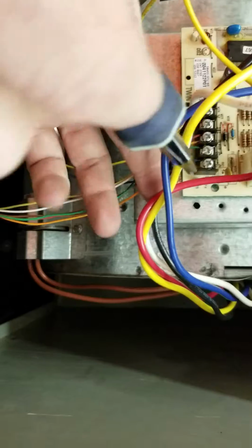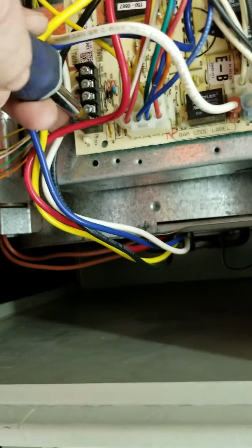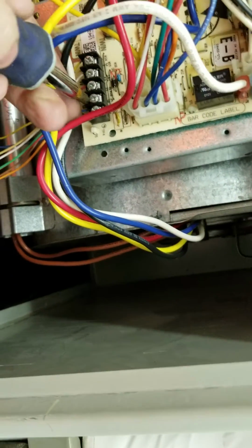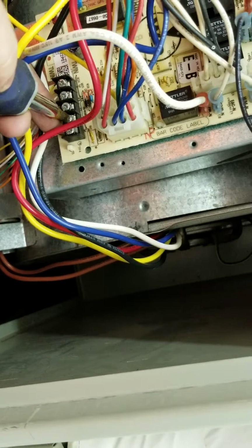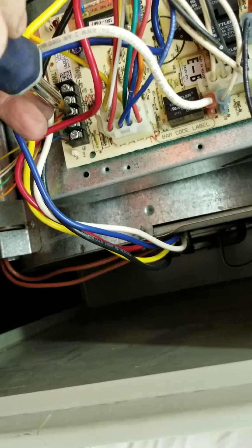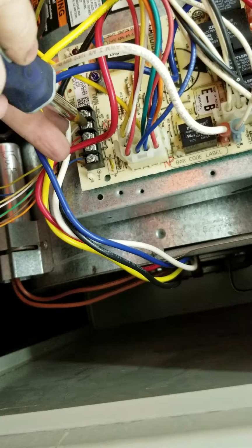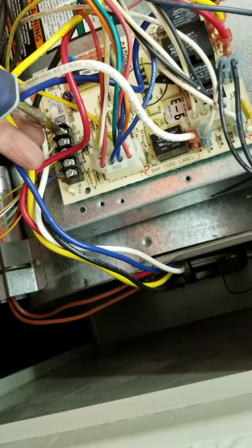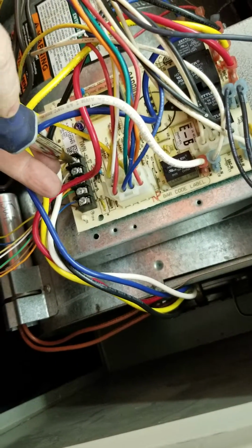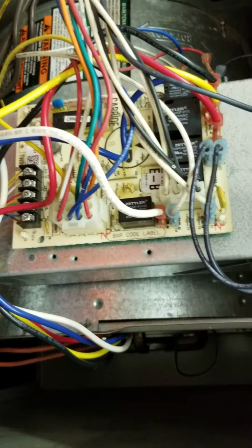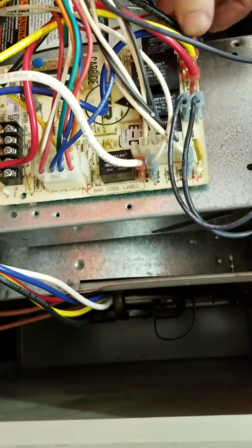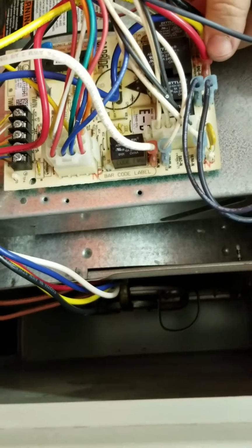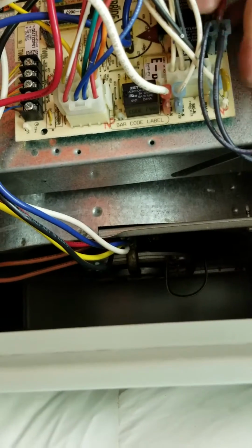Okay, now double check your connections, your control connections here at the furnace. You don't have to be real hard on these, because if you do too much, you'll twist it off of the printed circuit board, and then you end up buying a circuit board. Make sure all of the connections are tight to the board, including the high voltage ones. Just push on them gently. You'll know if they're loose, they'll move. All your pin connectors.